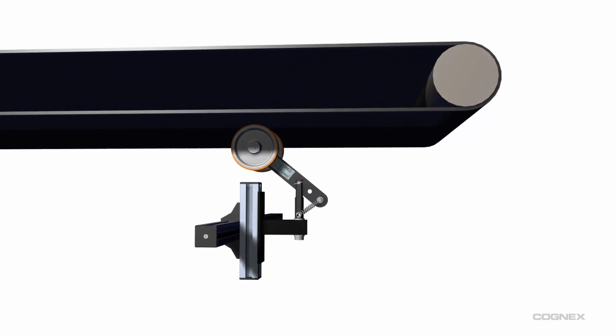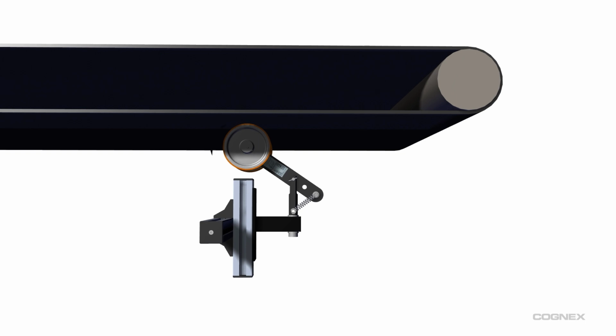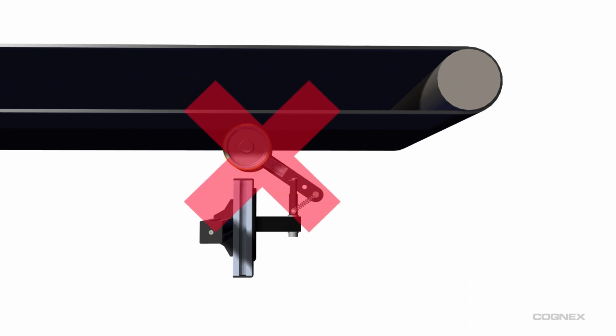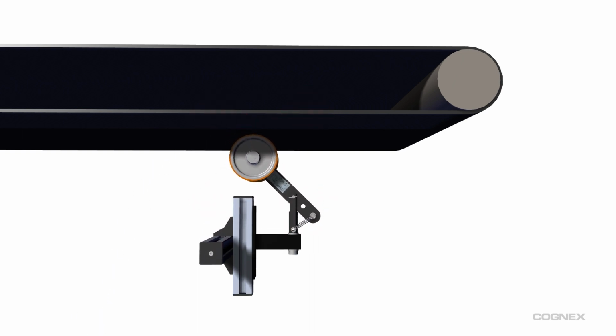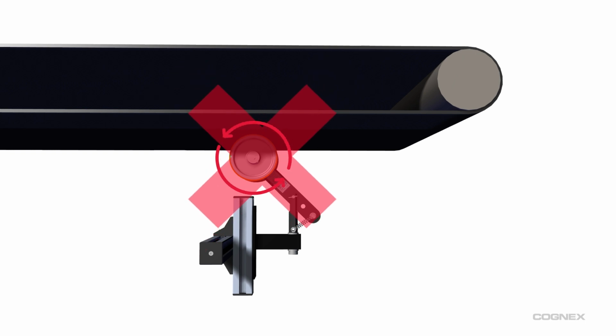If the encoder is installed too tight to the belt, it may cut into the belt. It is easier to tell if the encoder is too tight, as there will be belt shavings found on the ground. A cut-up conveyor belt will need to be completely replaced. Conversely, if the encoder is installed too loose to the belt, the encoder will slip, not spin correctly, and cause inaccurate speed being reported.